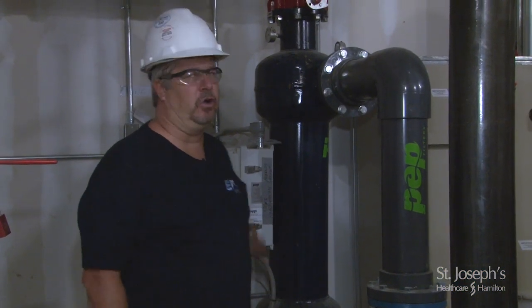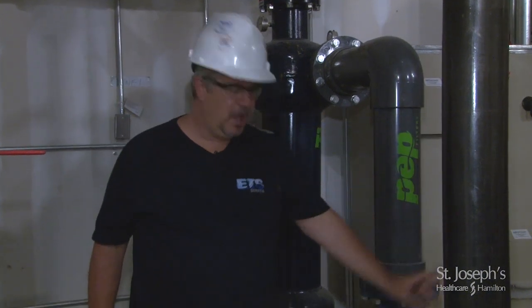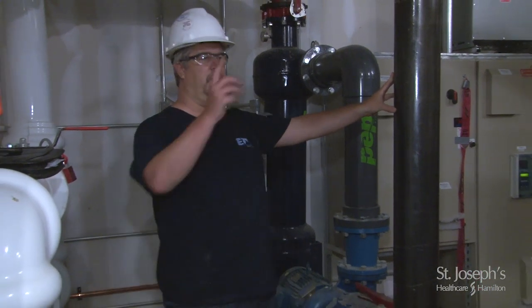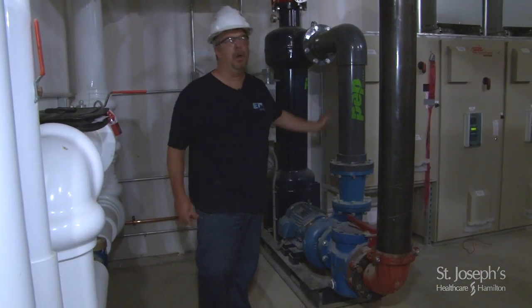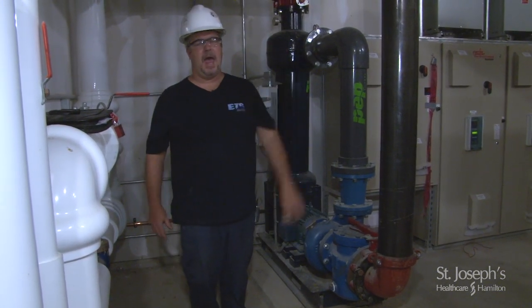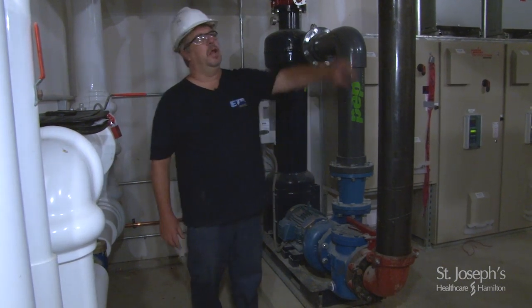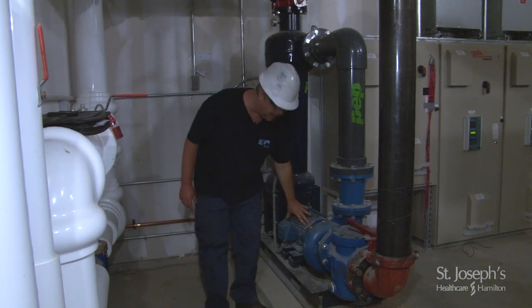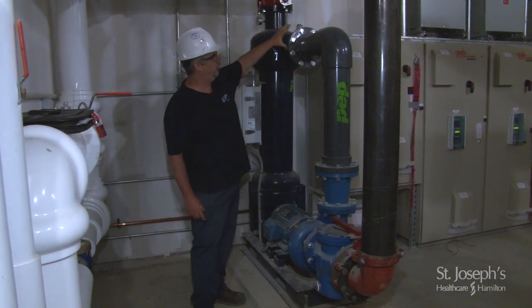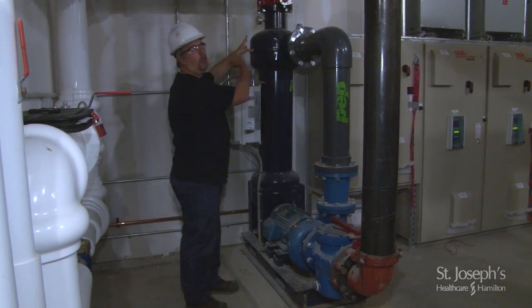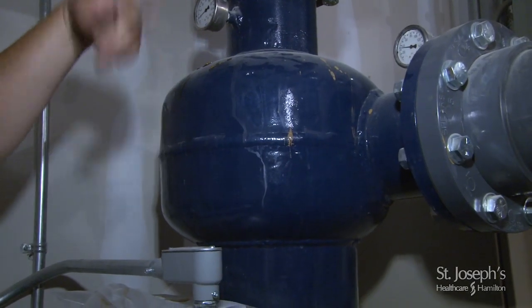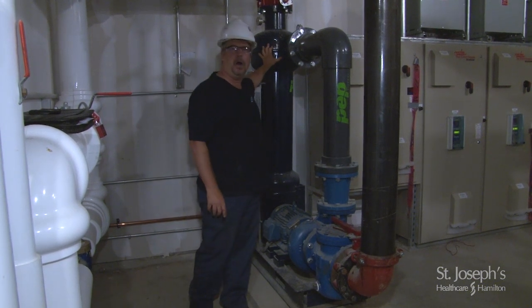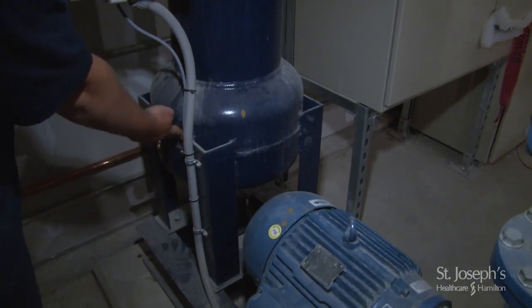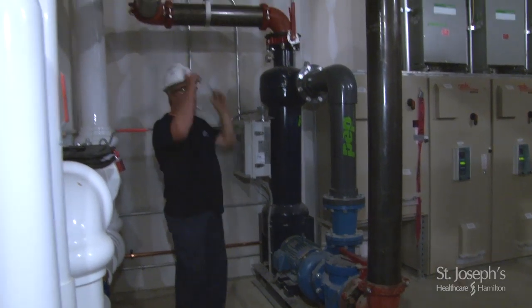We are looking at the PEP centrifugal filter. The sole purpose of this filter is to separate any hard solids within the water coming from the pumps and cooling towers, trapping them to prevent any of that reaching your chillers and pumps and causing premature failures. Basically, water flows in from outside out of the cooling towers, is pulled down through a pump assembly that you see right here below me, and is then flowed through this pipe into the centrifugal part of the filter. As the water hits this, it starts to turbulate, spinning in a very rapid motion. Any hard solids within that water will fall into this chamber and get trapped at the bottom of it. The clean water is then flowed back out and returned to go through that whole cycle out at the cooling towers again.